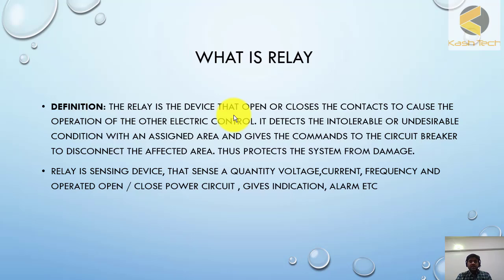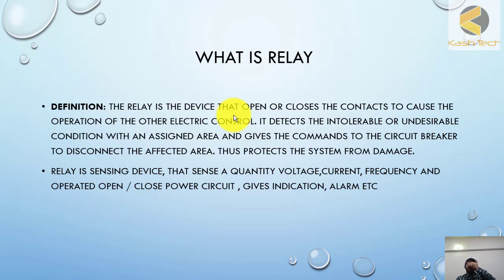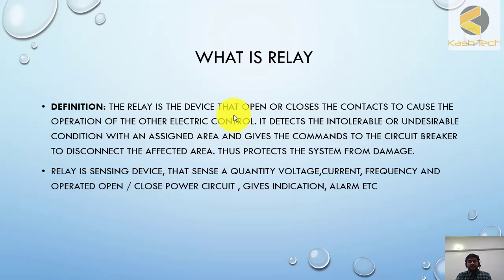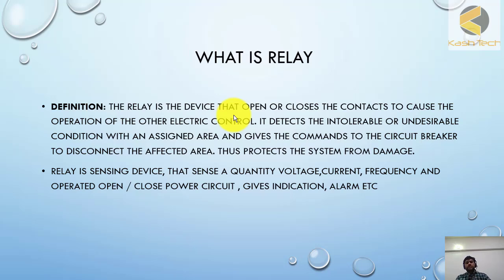I'll give you a relay example. In your house, voltages are coming at 110 volt or 220 volts. If the voltage increases - if your rated voltage is 220 and it increases 20 percent, 30 percent, 40 percent - what could happen? Your power equipment can burn. So what you can do is install an over voltage relay. That relay will monitor the voltages, and as soon as the voltage rises - for example, you have selected the setting - if rated is 220, if voltage goes beyond 250, it will trip and open the power circuit.